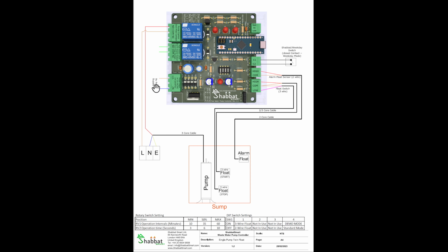Power supply to the unit: a 9-volt transformer, supplied with the unit, connects on this connection right over here. Then the alarm relay can connect to any kind of alarm, whether it's a buzzer or an alarm system with a text message or an email, etc. Then we have the pump relay. Live comes into the common, leaves out from normally open, and together with the neutral and earth goes to the pump.